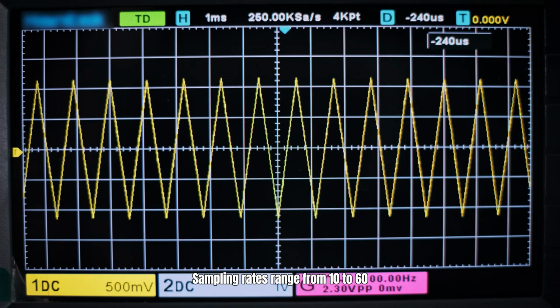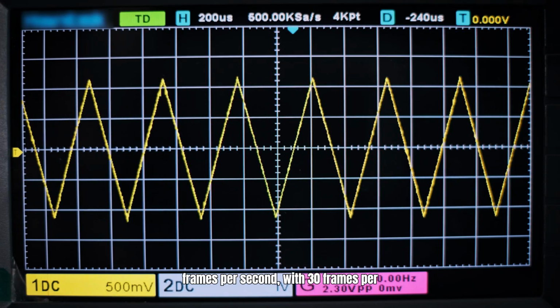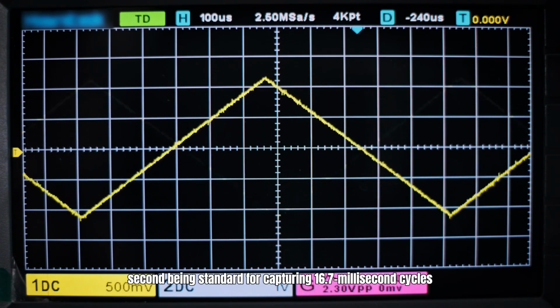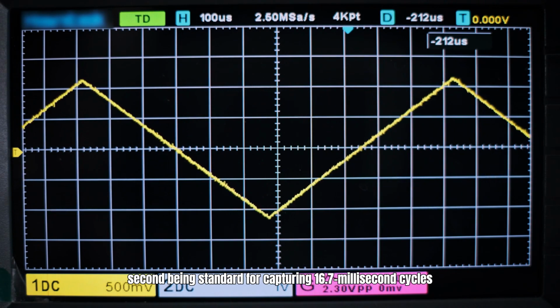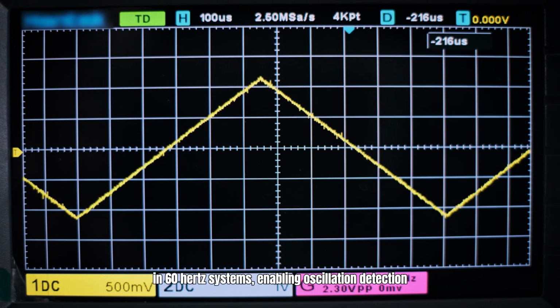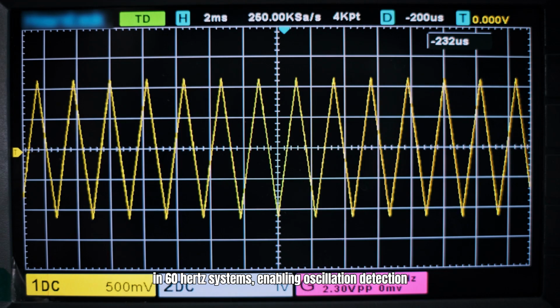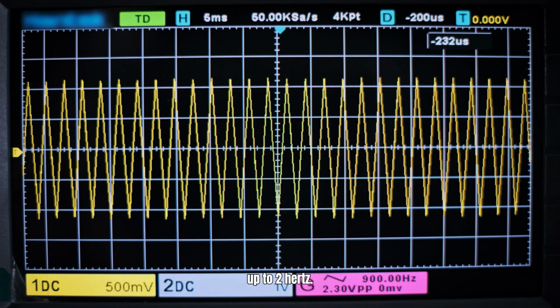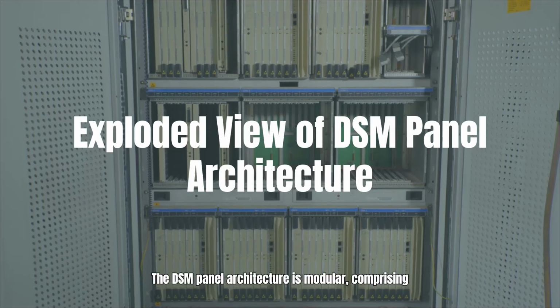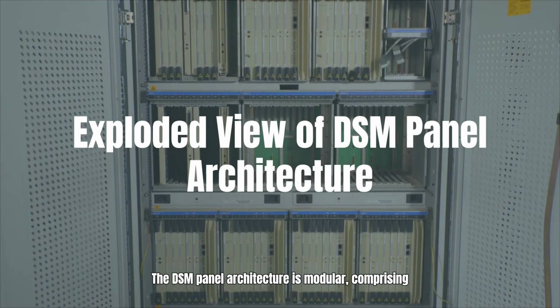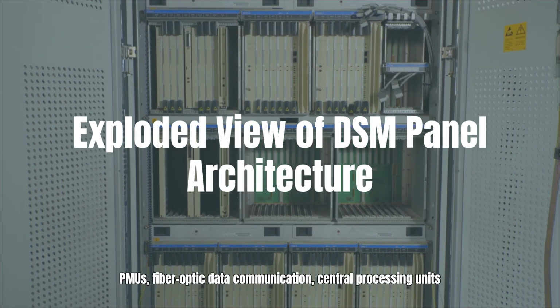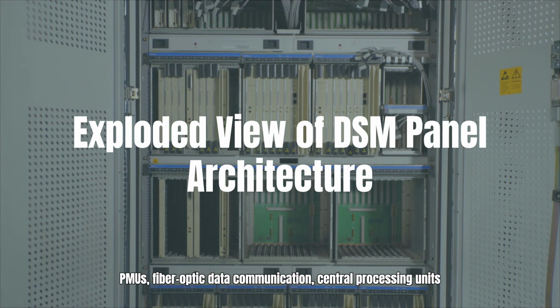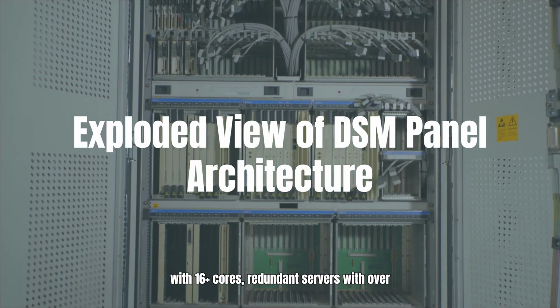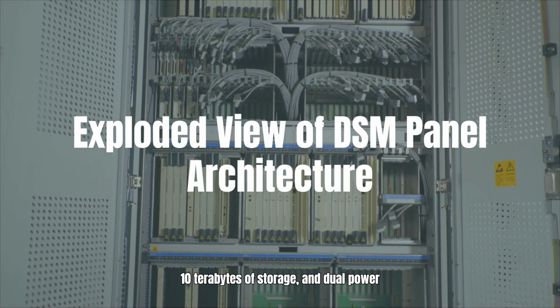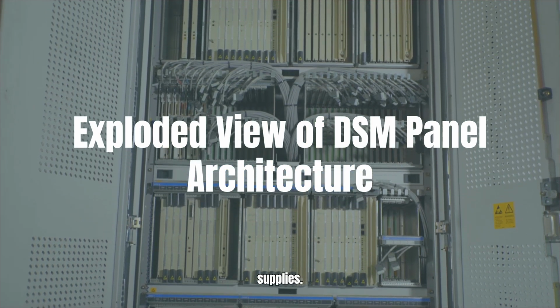Sampling rates range from 10 to 60 frames per second, with 30 frames per second being standard for capturing 16.7 millisecond cycles in 60 Hz systems, enabling oscillation detection up to 2 Hz. The DSM panel architecture is modular, comprising PMUs, fiber optic data communication, central processing units with 16-plus cores, redundant servers with over 10 terabytes of storage, and dual power supplies.